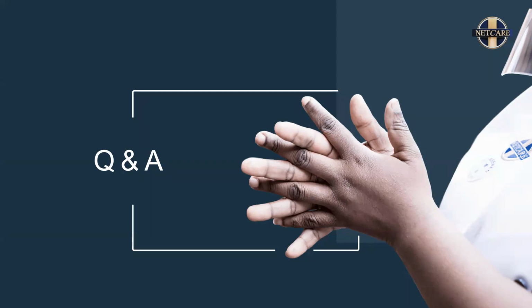All right, so can one close the dampers to tea rooms without windows only? This allows for more fresh air. Jaco, any thoughts? So a combination of both would not make any difference to the fresh air component. To have mechanical fresh air and openable windows is more fresh air. It gives you more air changes in that particular area. And I wouldn't recommend closing any dampers, because the design for that system of fresh air was developed to ensure that there's a certain quantification of fresh air in that particular area. So I would just open up a window or two, or all of them. It will give you a benefit over and above what the mechanical ventilation is providing you. So the question is, open the dampers.